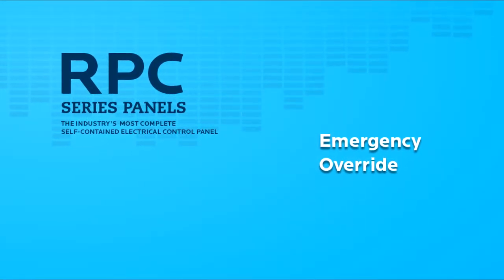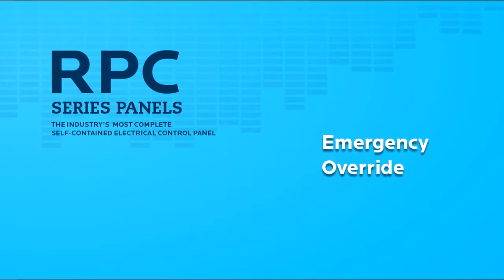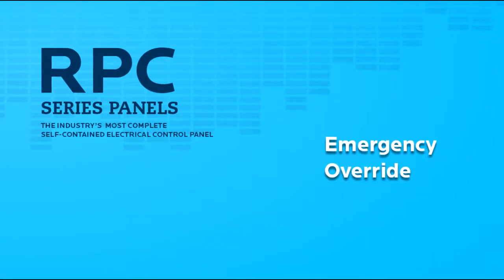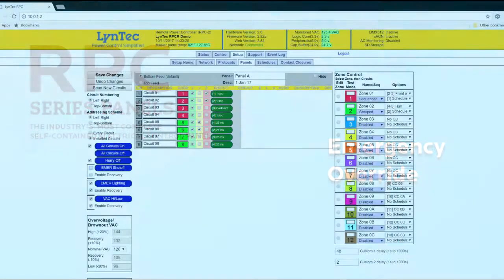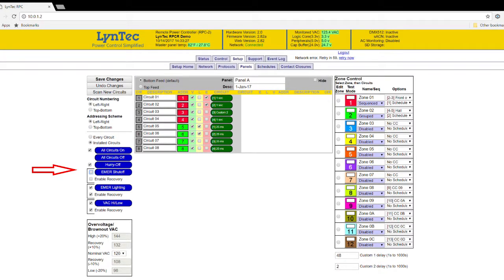Next, let's review the RPC panel's emergency shutoff, which is typically used to interface with a fire alarm system. To enable this function, click the checkbox next to the emergency shutoff button. In the event of an emergency, a fire alarm will activate the contact closure, shutoff mode will be activated, and designated circuits will turn off immediately.